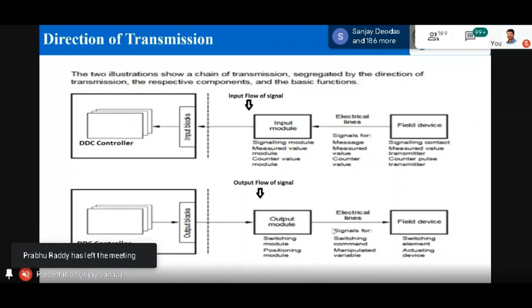If the level goes less than 75 minus deadband—say the deadband is 10, so less than 65—then the DDC controller will give a signal for the pump to start, so that it starts filling the tank again. This is how any control loop works, and anybody with a little knowledge of instrumentation will understand this.